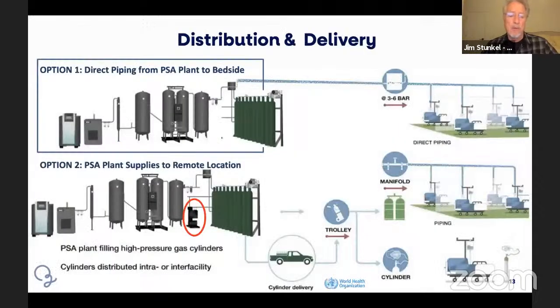Here are two images of distribution and delivery systems. Option 1 is direct piping from the PSA plant to the bedside. You can see the components of the plant and the green cylinders attached as a backup supply should the plant need servicing, and the blue line that goes across to the hospital beds. That's a direct piping system, in which case the plant needs to be very close to the hospital, maybe on an exterior wall or an adjacent building.